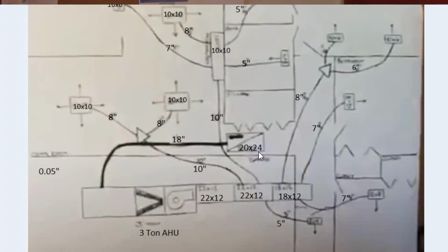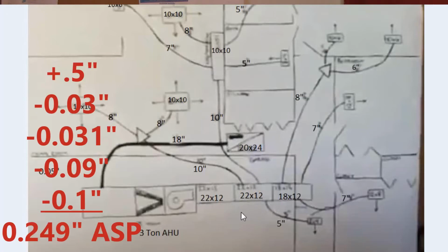And then what's right behind that? Well, the filter itself. The drawback to a lot of these is you're limited to a 1-inch filter. So we're going to use just a standard 0.1 for the drop on that. So we'll take that 0.1, add it into our equation, and we will come up with our available static pressure. In this example, my available static pressure is 0.249.